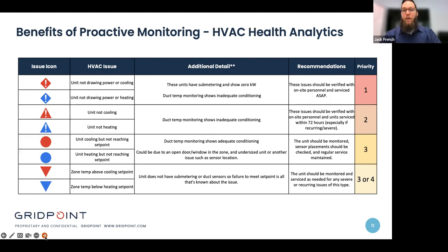The next two exceptions would be priority three. So unit cooling but not reaching set point, or heating but not reaching set point, very similar. But in this case, the duct temp monitoring shows that there actually is adequate conditioning. So in the example that I keep coming back to, where we have a 70 degree occupied cool set point and the duct temp shows maybe 55 or 60 degrees, well, that's cool air.